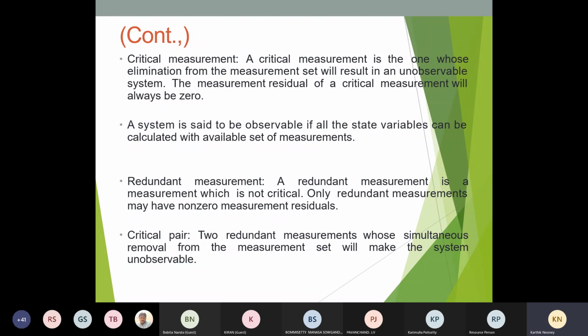These definitions or terms will come across whenever you are searching for state estimation with phasor measurement units in power systems in IEEE, Springer or ScienceDirect papers. A lot of them talk about critical measurements and these things. A redundant measurement means a measurement which is not critical. That means if its residual is not 0, then we call it a redundant measurement. That's what they have said here. Only redundant measurements may have non-zero measurement residuals. That means they will create an error.